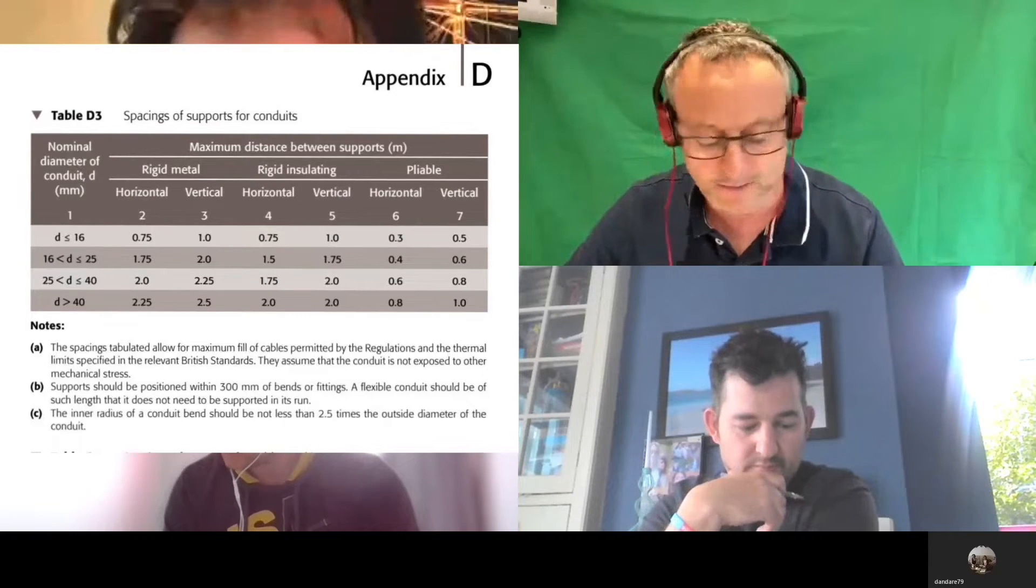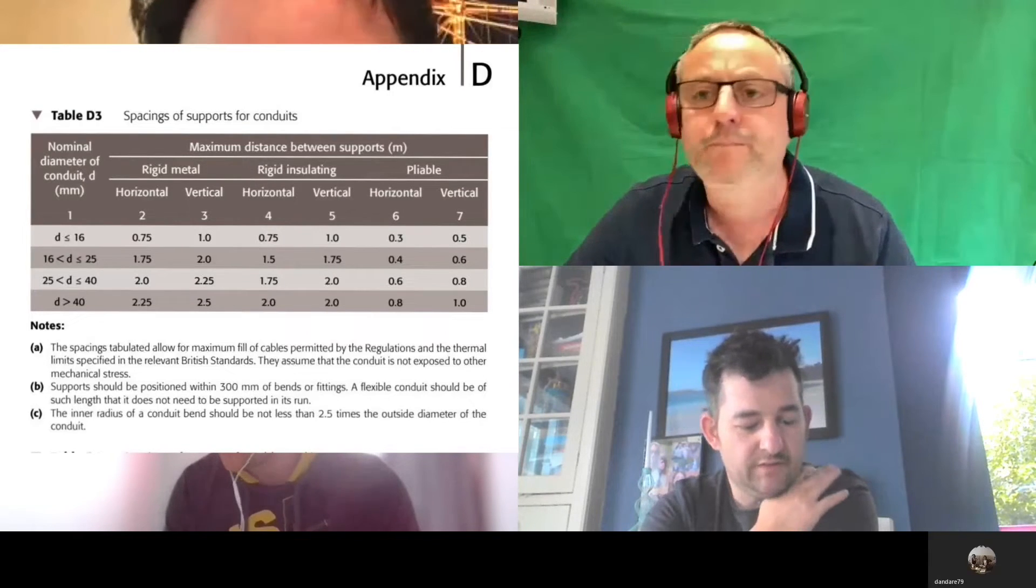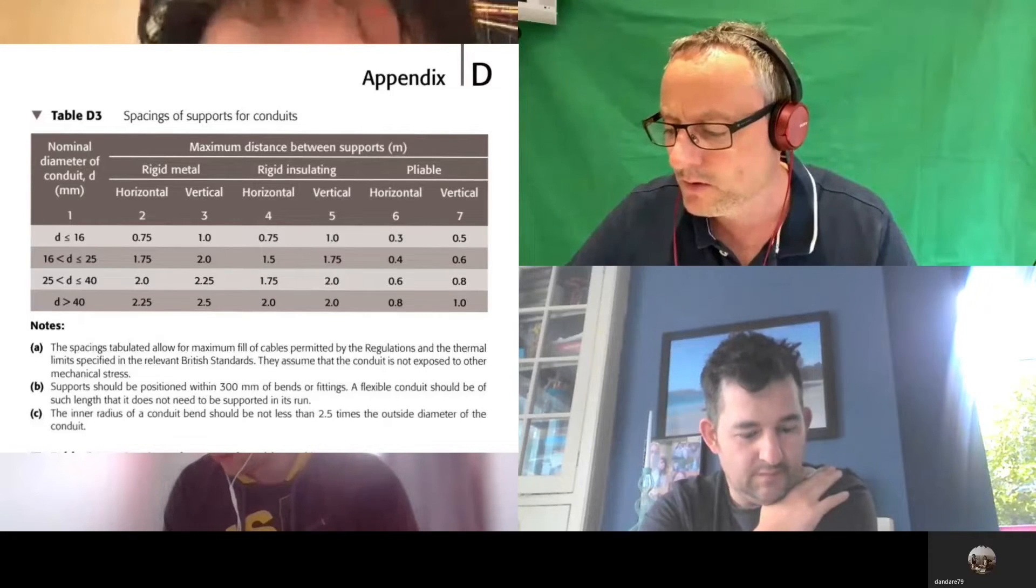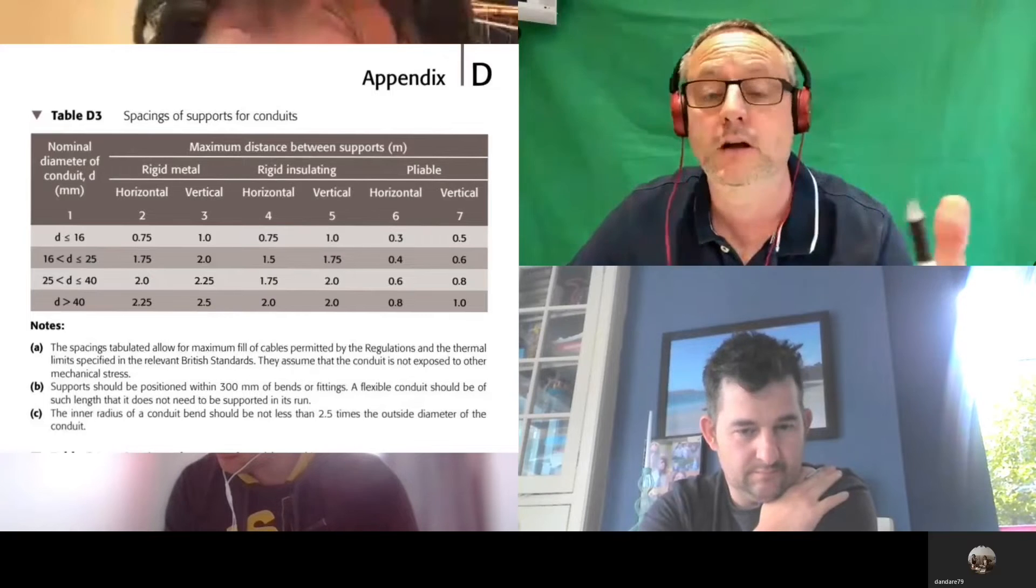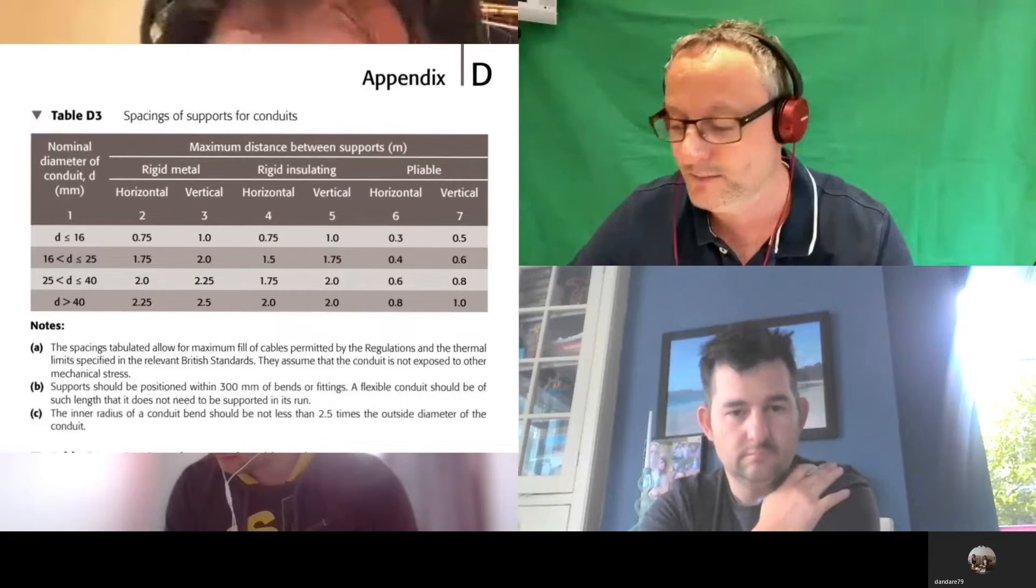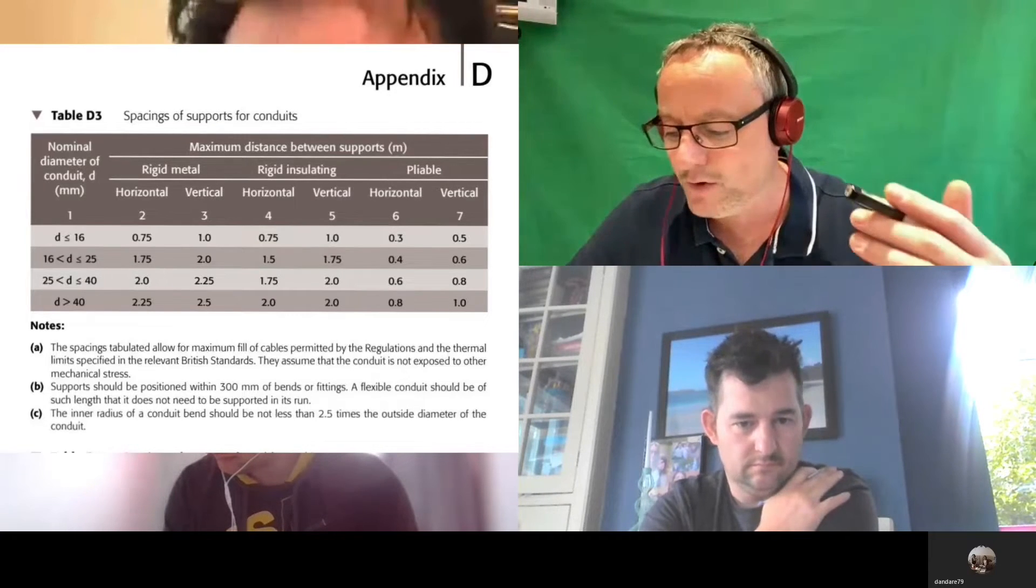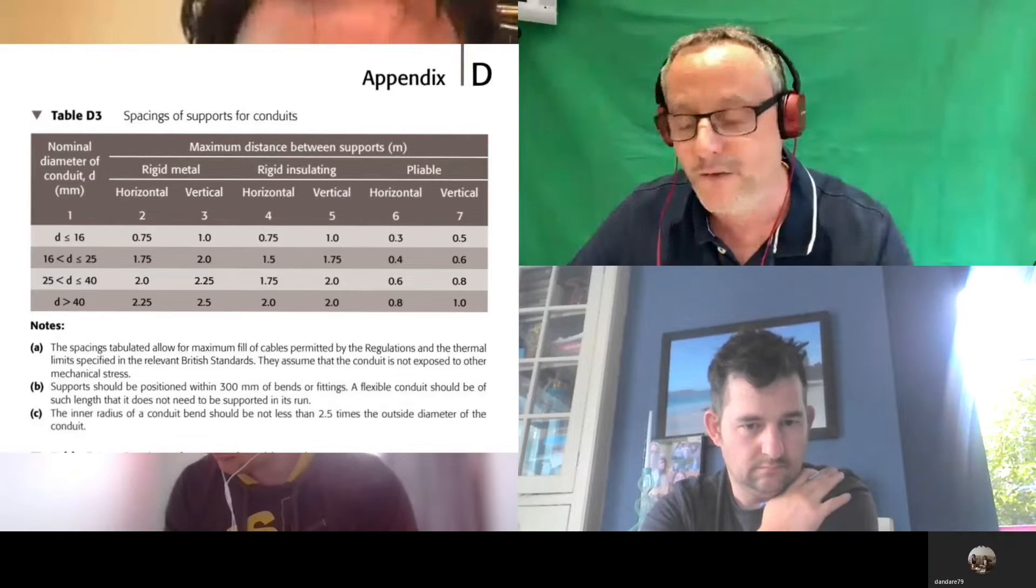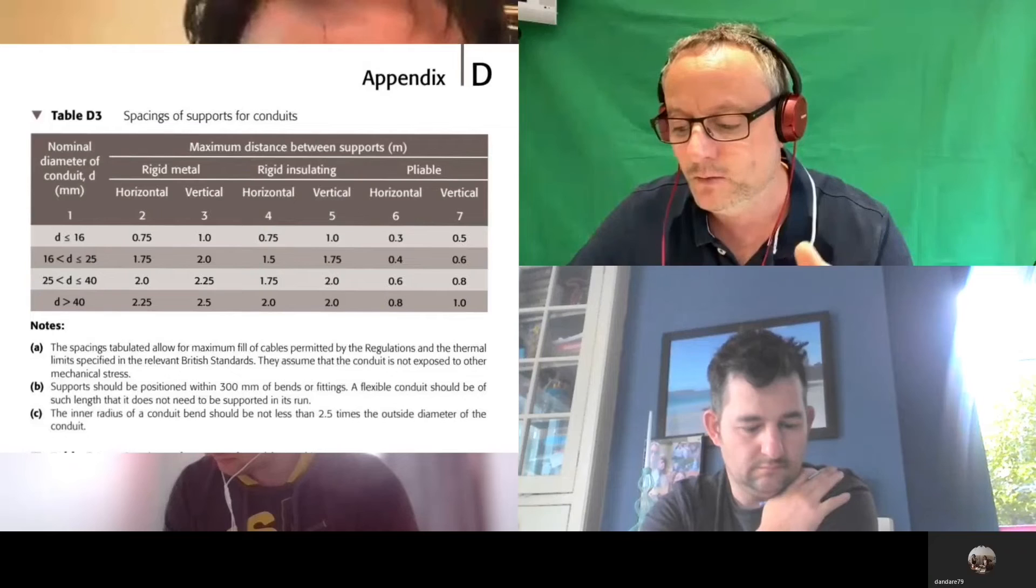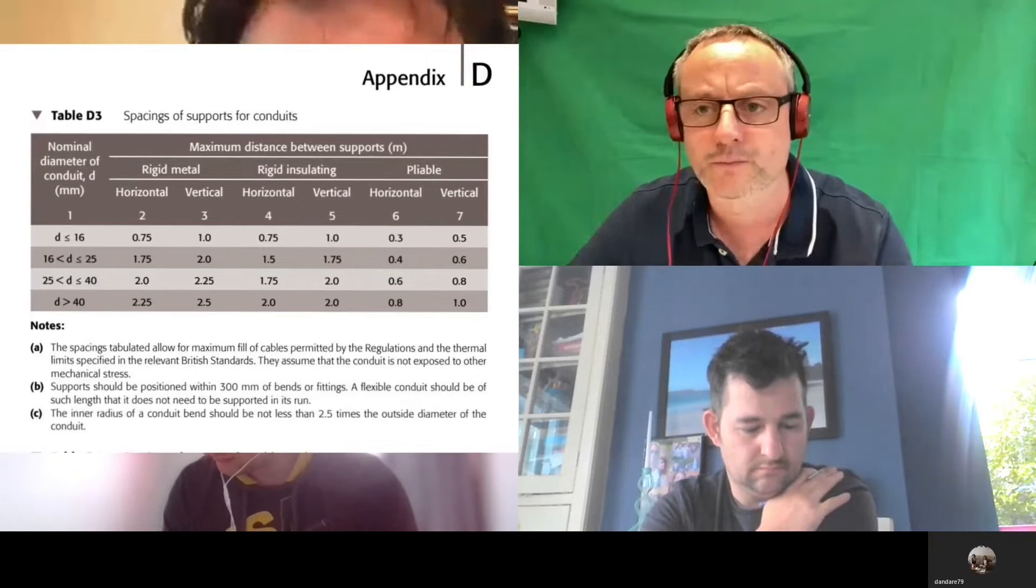We can clearly see that that one is PVC conduit. So if I said to you you had 16mm conduit horizontally, the supports would need to be at what intervals as a maximum? 0.75, and vertical, one meter. That's the maximum we can go. We can go more frequent; we can't go less frequent than those dimensions. If I said to you it was 25mm metal conduit, what's it looking like now for horizontal?